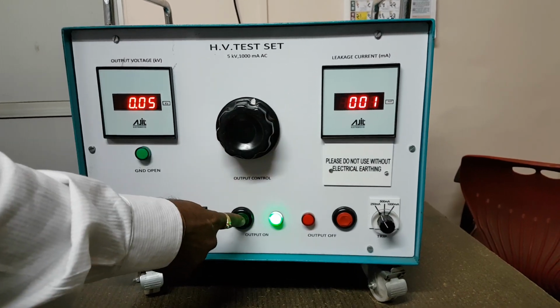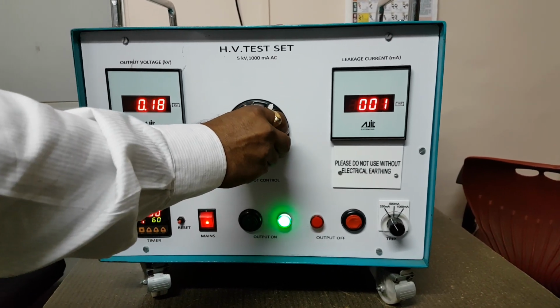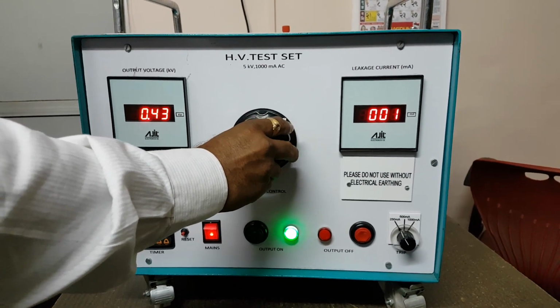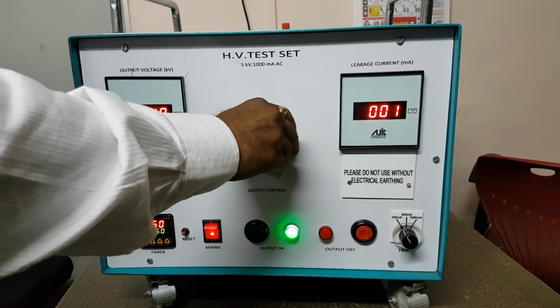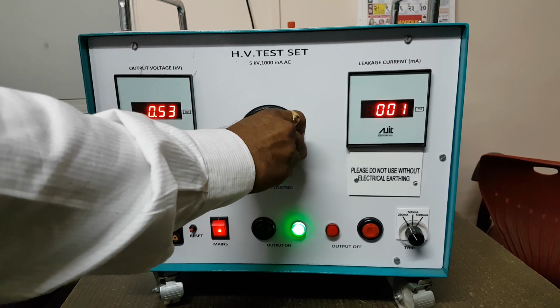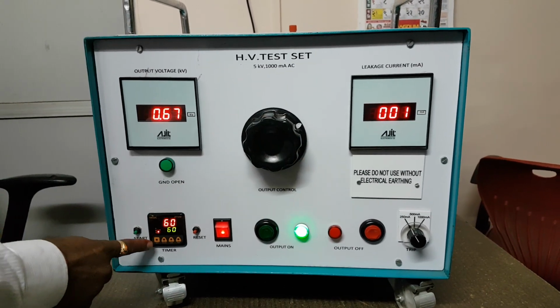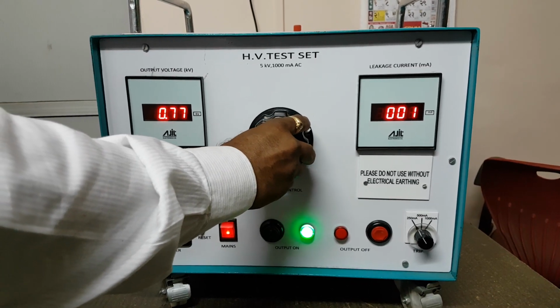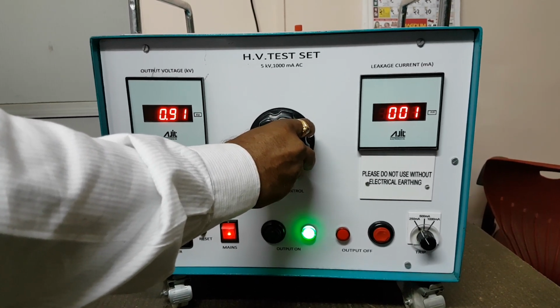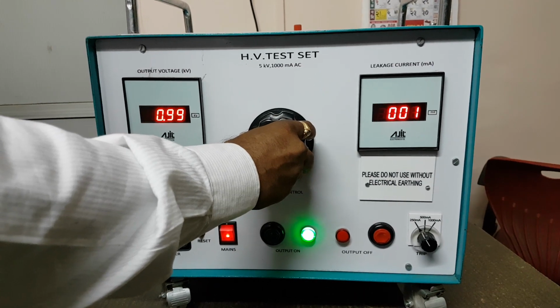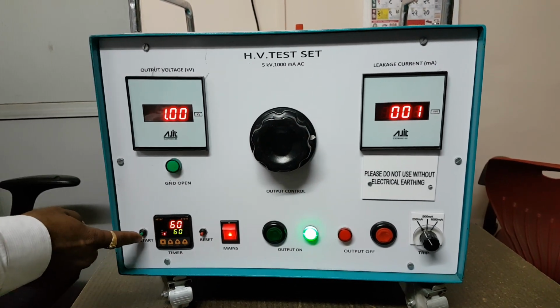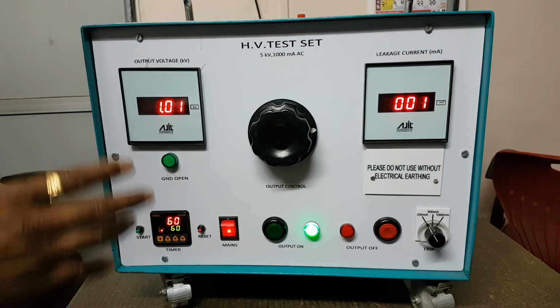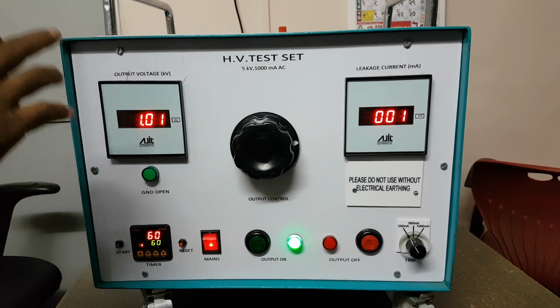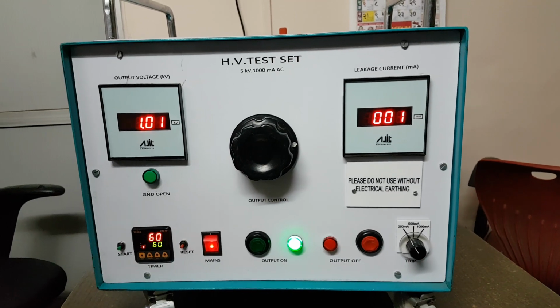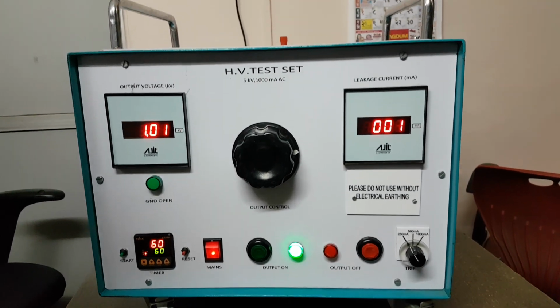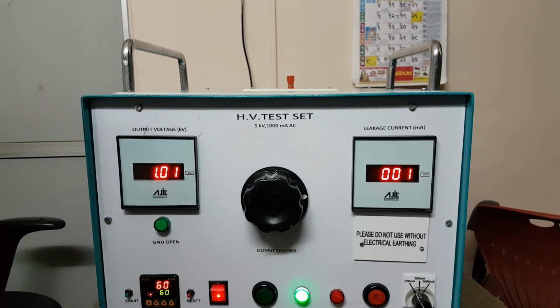Like this, we have to put on the output and we have to turn the voltage control knob. If suppose our test is of 1 kV and for 60 seconds, then we have to set this timer first at 60 seconds and output at 1 kV and start the timer. This way we can set the output voltage on the display and get the output between the output terminal on the top panel with respect to ground.